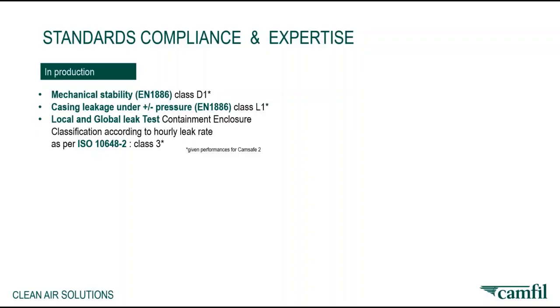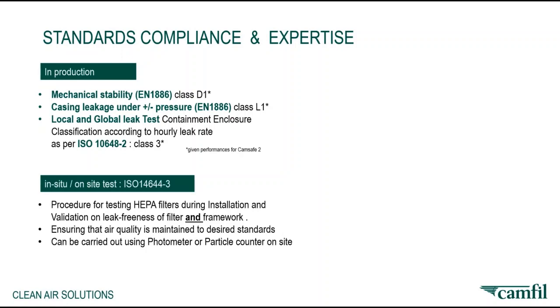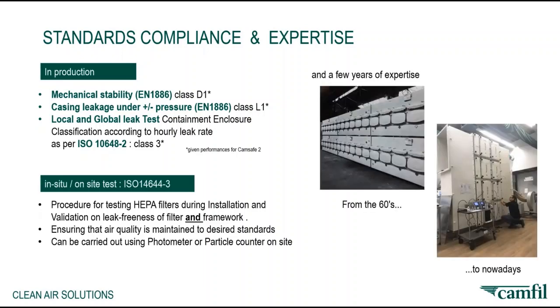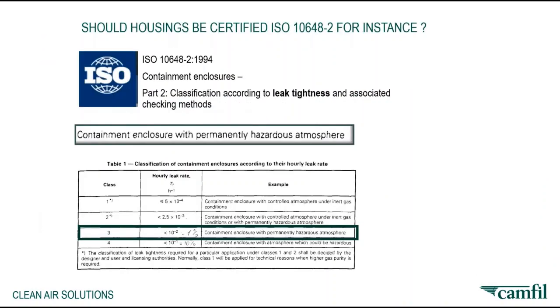So first, compliance with standards and requirements. The main standards our products will comply with are EN 1886 and ISO 10648 in production. And exactly as for HEPA filters, the ISO 14644 will challenge housing performances on site together with the HEPA filter. Of course, a few years of experience from the 60s to nowadays helps to comply with requirements. But despite the fact products are airtight by design, as Volker will introduce just later, some products are 100% leak tested, typically the case for CamSafe BIBO housings for BSL environments. Of course, other individual leak tests can be done on request for any housing that includes a HEPA filter.